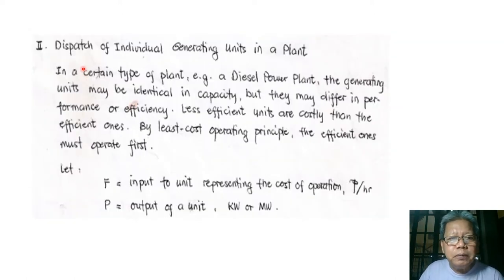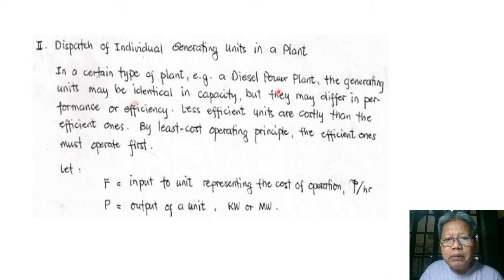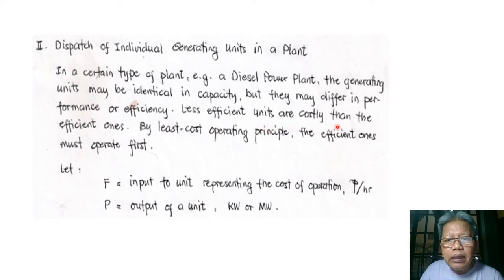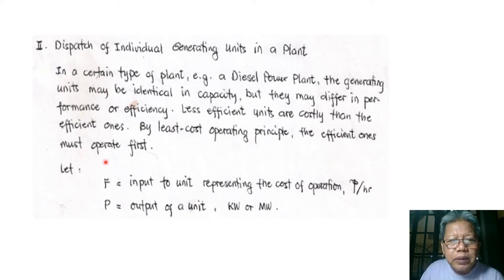Now, the dispatch of individual generating units in a plant. In a certain type of plant, for example a diesel power plant, the generating units may be identical in capacity — say 50 megawatts each — but they may differ in performance or efficiency. Less efficient units are more costly than efficient ones, so by the least-cost operating principle, the efficient ones must operate first.